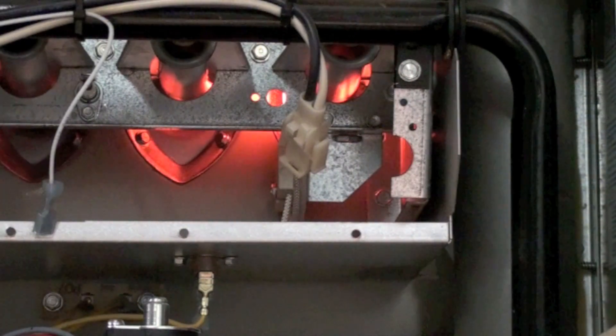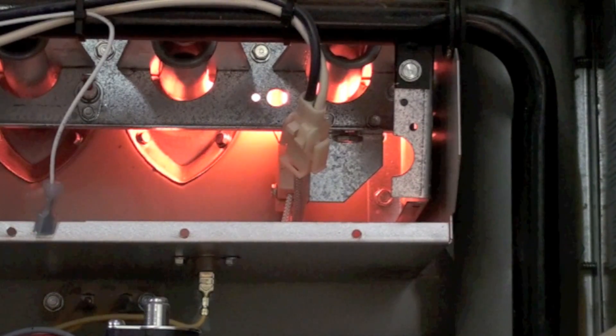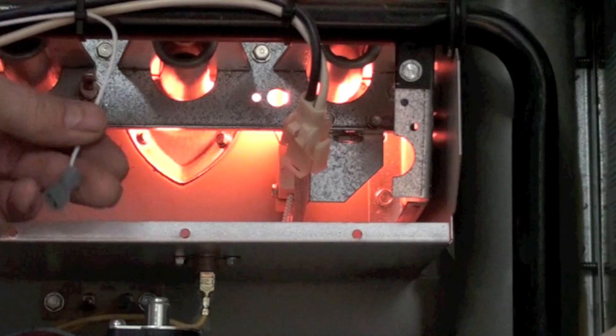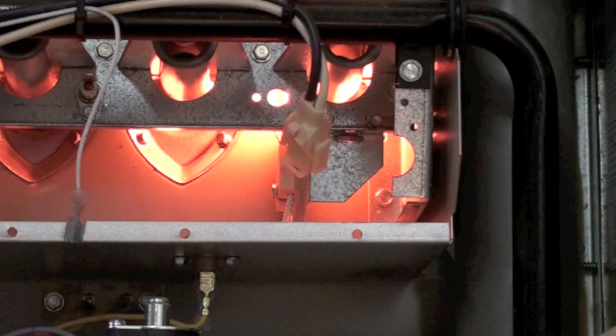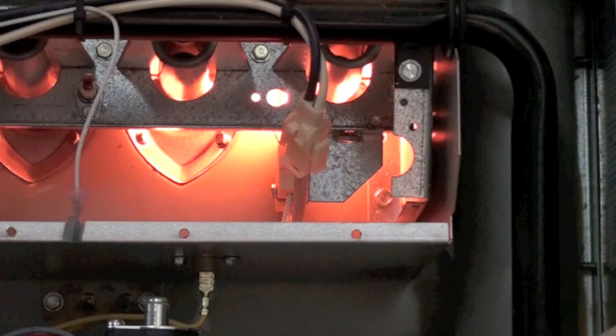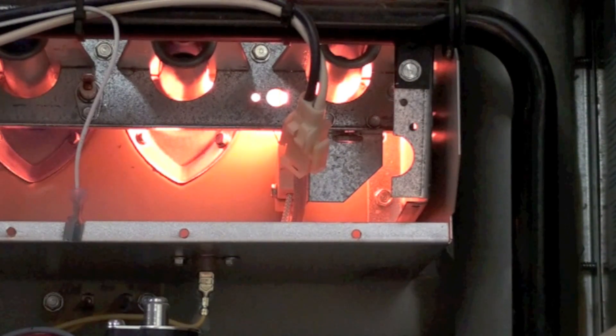The flame rod is nothing but a piece of stainless steel shaft that stays inside the flame. This wire here goes to it to conduct the signal back to the board down below. And if it doesn't sense the proper signal, then it's going to go ahead and shut it off.